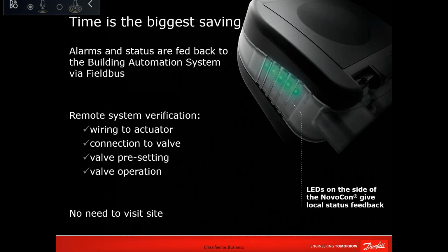Can we remove the BTU meters from the system if we are using Novocon with the flow indication and temperature sensors? It's based on what is the usage of the BTU meter. A BTU meter is an energy calculator. It will gather supply and return chilled water temperature like the Novocon does, and it will measure the flow with an ultrasonic flow meter or magnetic flow meter.